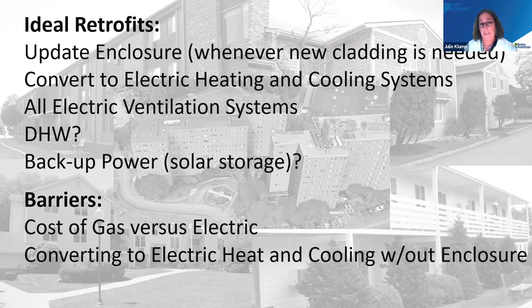And again, backup power. I think the big issue for us converting to electric heat, which people can probably relate to, is that if you don't invest in a robust enclosure in a northern climate—where the design degree for heating is well below zero—you might not be able to accommodate the heating loads your buildings and residents want with an electric heating system, or you'll at least lose a lot of that system's efficiency.